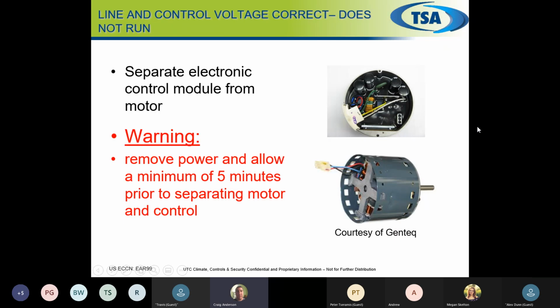Another way to check our older motors, whether it's our furnace or other manufacturers, is that the motor can be separated. 90% of the time, it was the end bell on the motor. As soon as you took it apart and looked at it, the capacitors inside that little head were blown up. The acid is coming out of it. It was pretty easy to determine what the problem was at that time, it was in that little head. But you can separate them and test this bottom part of the motor.